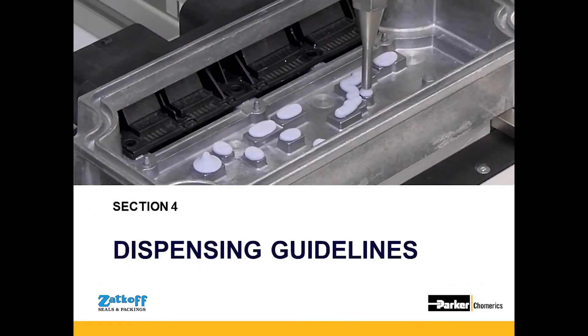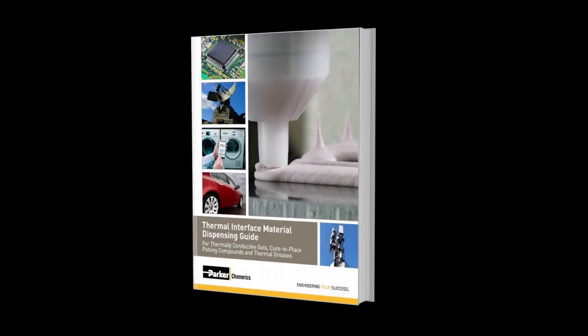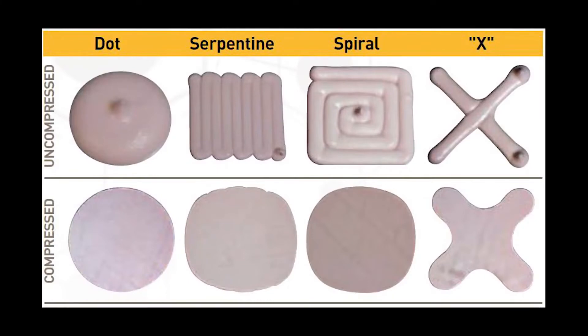Now getting into dispensing guidelines and parameters for selecting dispense equipment. When dispensing thermal gels and putties, there are many tips, tricks, and considerations, all found in our thermal interface material dispensing guide. The slide shows dispensing patterns before and after compression — it's important to consider what gaps will look like and how much space the gel will take up after compression. Key considerations also include cleaning the part prior to dispensing using IPA or a solvent solution.